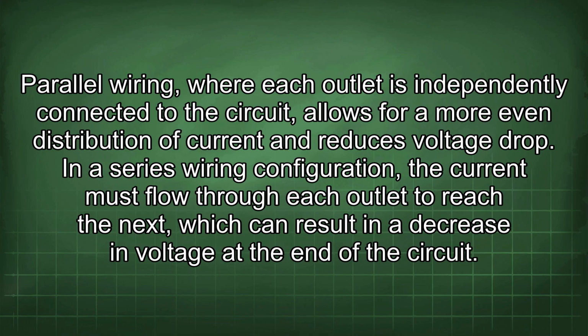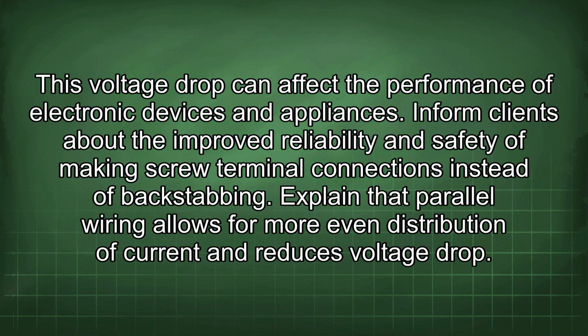and reduces voltage drop. In a series wiring configuration, the current must flow through each outlet to reach the next, which can result in a decrease in voltage at the end of the circuit. This voltage drop can affect the performance of electronic devices and appliances.